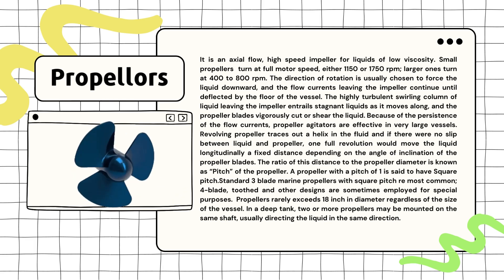Usually we find standard three-blade marine propellers with square pitches. Sometimes for special purposes, people use four-bladed propellers, toothed propellers, or other designs. Regardless of container size, propellers used this way are usually not larger than 18 inches in diameter. In really deep tanks, you might see two or more propellers on the same shaft.